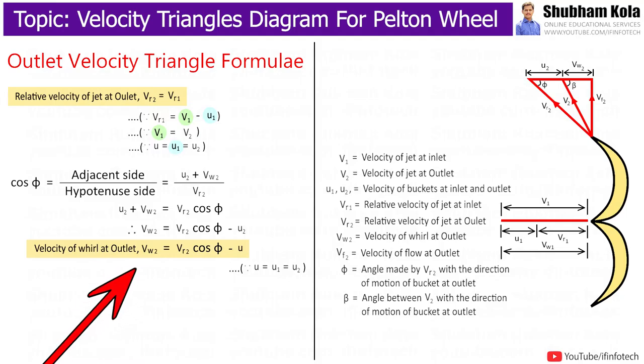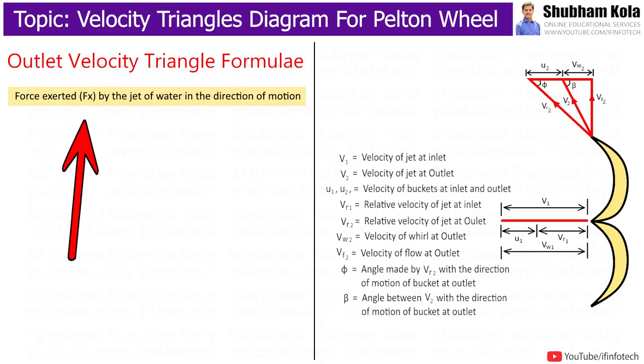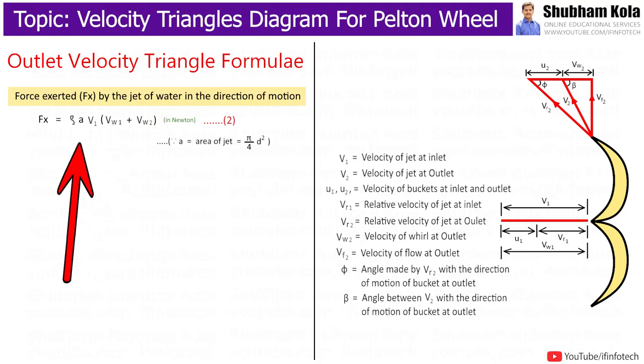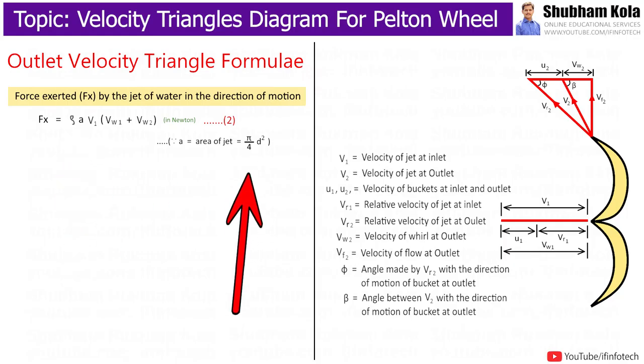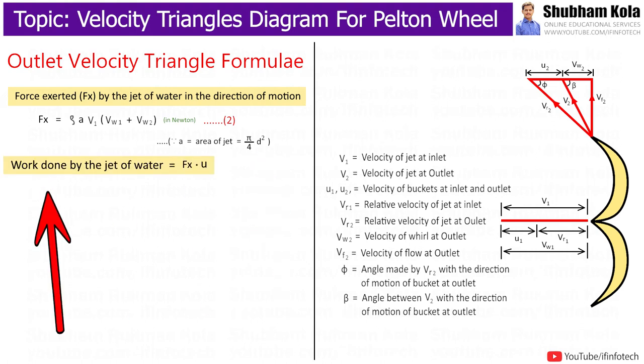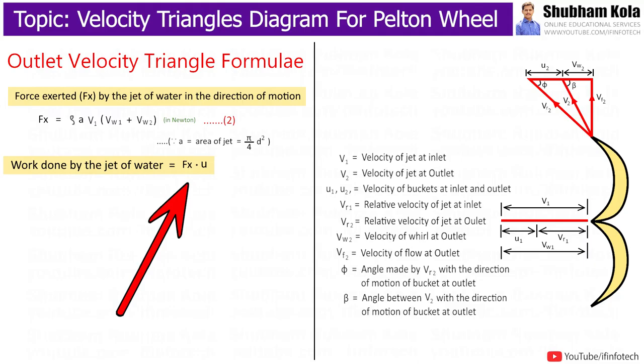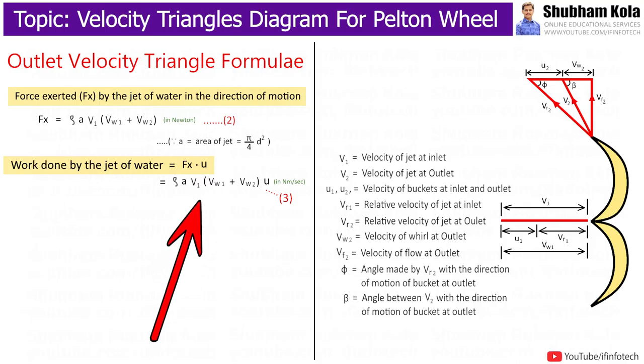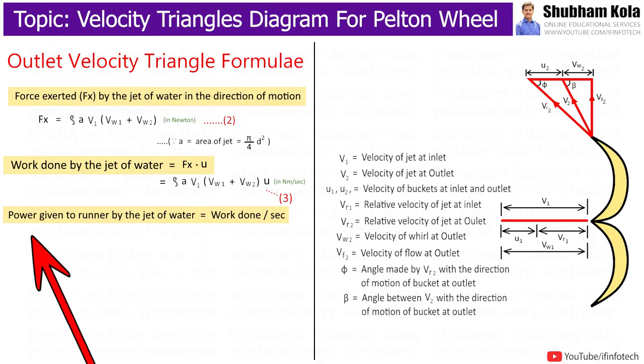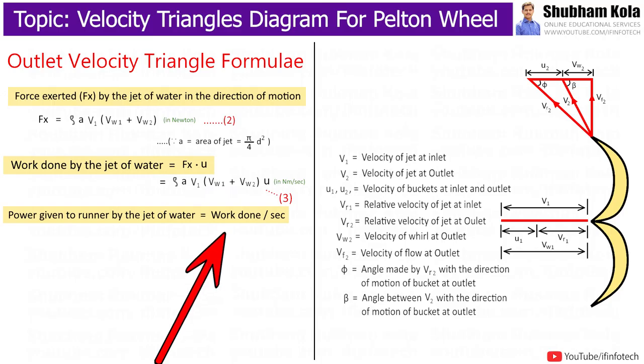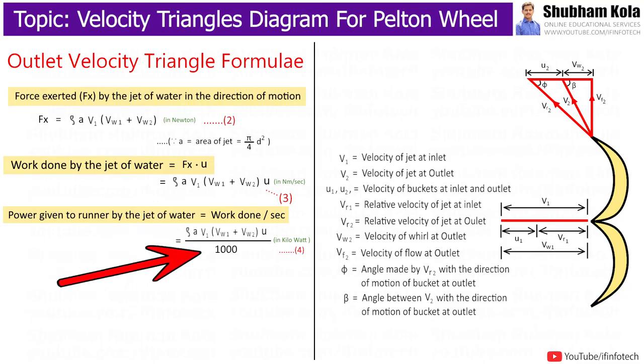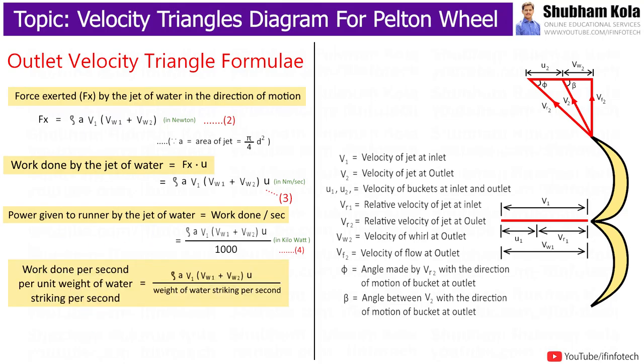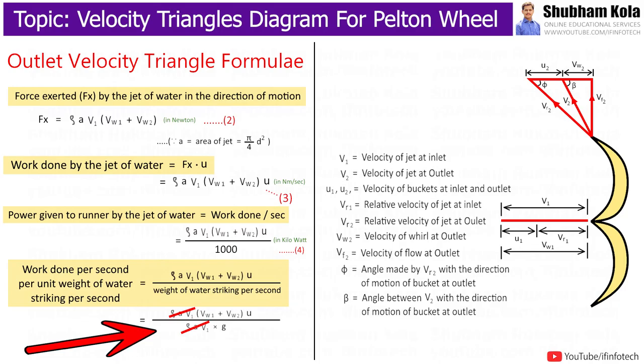We keep this value aside for use in the work done calculation. The force exerted by the jet of water in the direction of motion is given by Fx = ρaV1(Vw1 + Vw2), where 'a' is the area of the jet = (π/4)d². Work done = Fx × U. Power given to the runner equals work done per second, divided by 1000 to get kilowatts. Work done per unit weight of water striking per second is obtained by dividing by ρaV1g, which gives Equation 5.